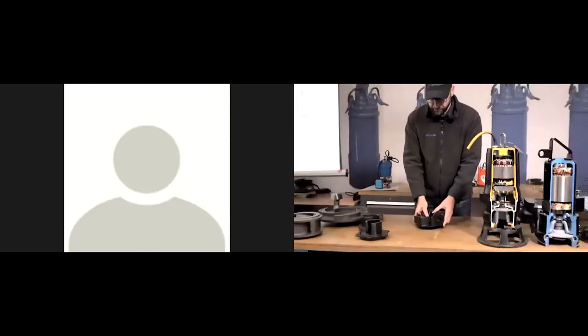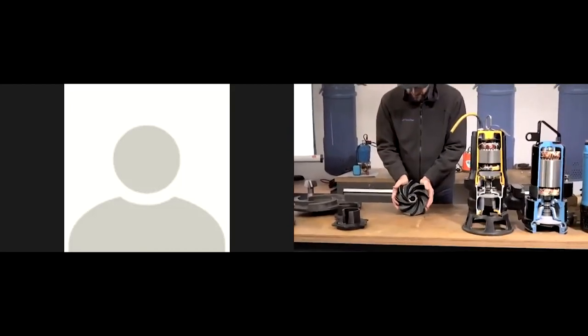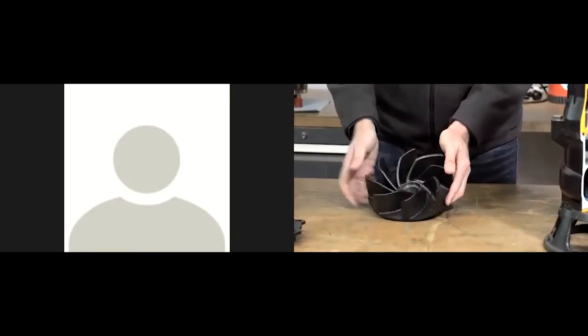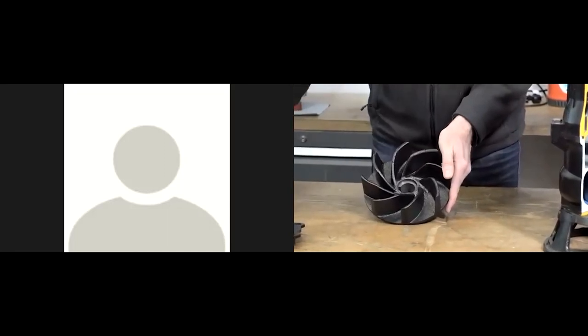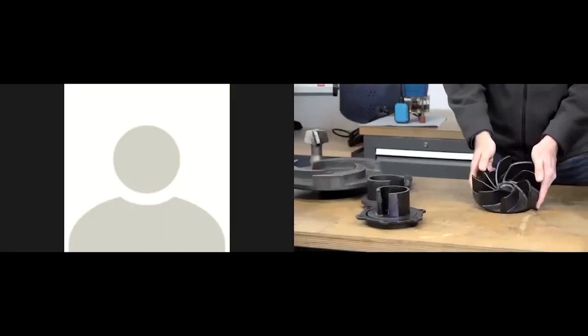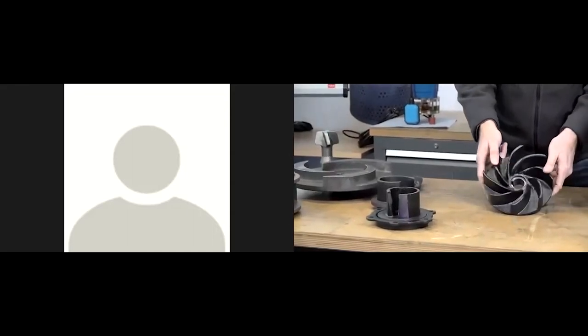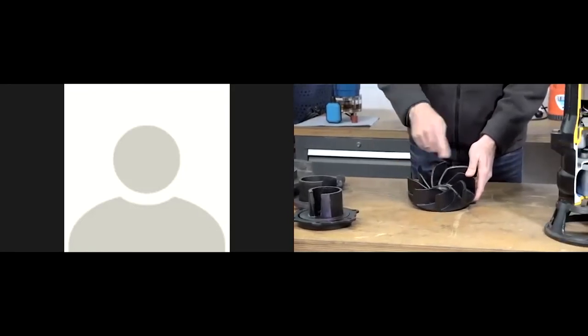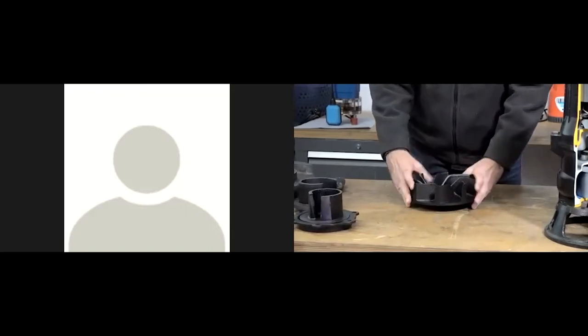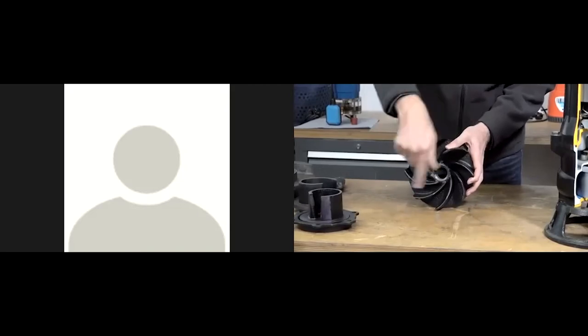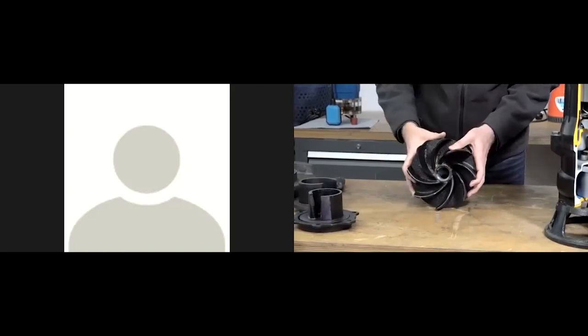Looking at a typical example of this impeller: its shape is round, like all other impellers. We have the impeller vanes — in this case it's a multi-vane impeller, though vortex impellers can also have only three vanes. The general design has a ground plate, the vanes all similarly oriented, and this design creates a vortex streaming that is responsible for the pumping effect.